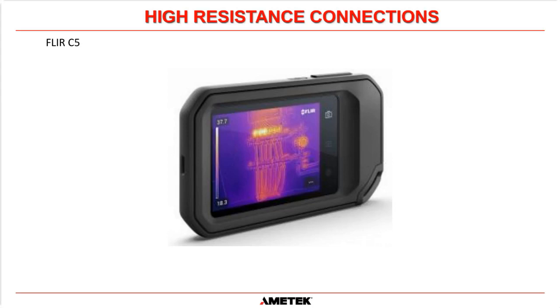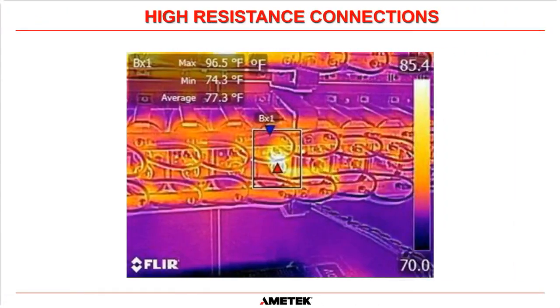And the best way to find high resistance connections is to do a thermal scan. And all of the AMETEK SCI field service engineers who go out to the plants and perform regular maintenance all have a FLIR C5 camera as part of their standard equipment, exactly the camera that you see here. So every time we come out and do a PM on one of your systems, we do a thermal scan. And I'm going to show you two instances within the last couple of years where high resistance connections have been found. So you can see in this picture here, these are the AC capacitors on the output of one of our UPS systems. And there are two wires going to each AC capacitor, and they're connected with a push-on crimp.